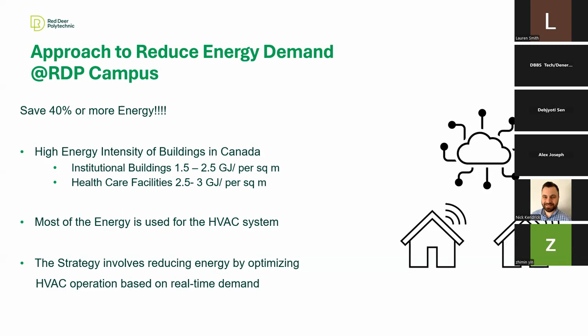So I'll move to the next slide. In our building, our approach is to put in air quality sensors, occupancy sensors (people counters), gas meters, and energy metering. We're metering this pilot building and measuring the baseline where it's sitting right now, with distributed sensors around the building monitoring air quality. Based on this data, we make decisions using AI algorithms in the BMS, the building management system, on how to operate the HVAC.